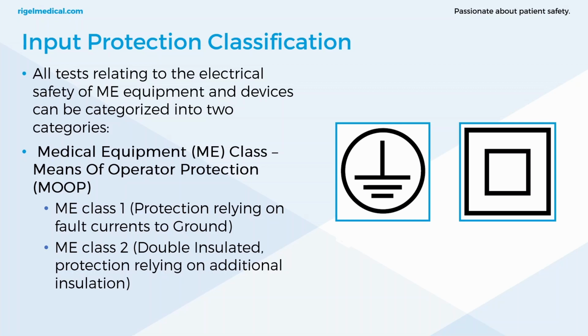Input protection classification. You've seen these symbols before. Class 1, which is relying on the fault currents to ground, and Class 2, which is double insulated. Protection is relying on additional insulation. So a symbol on the left, Class 1, and on the right, Class 2. These are typically found on the rear of the instrument, close to the power supply. As experienced biomeds, you can be well aware of these types of symbols that are available to you. Sometimes they're slightly different. You might have an equipotential symbol there, but they all effectively mean the same thing.